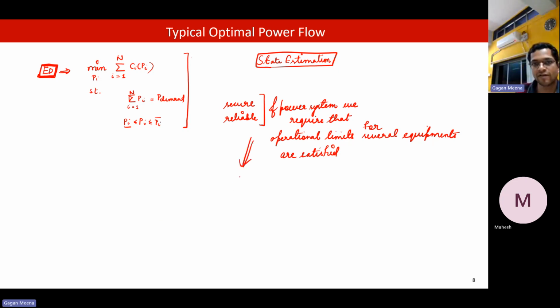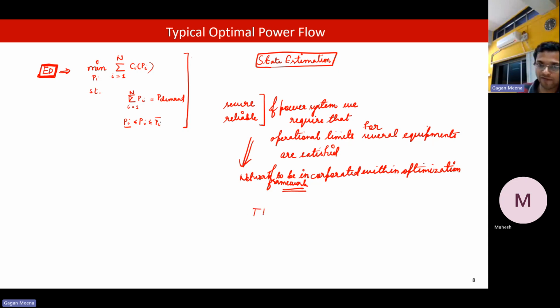And therefore, we want the network to be incorporated within this optimization framework. This transmission line is also one of the equipments, and we want the flow over a transmission corridor or transmission line to be below its thermal limit. Otherwise, increased loading can damage the line. The sag can increase and it can even melt. The conductor can melt.